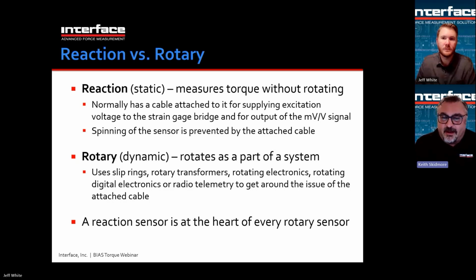A rotary sensor, on the other hand, uses some type of scheme to allow it to spin round and round without the cable becoming an issue. That could be slip rings, rotary transformers, or a rotating electronic scheme with, say, induction power transfer, which could be digital or analog. You can even use radio telemetry to broadcast the data signal across using, say, 2.4 gigahertz Wi-Fi, for example. Basically, a reaction sensor is at the heart of every rotary sensor. So you make a torque sensor, and then instead of soldering a cable to it, you add extra things to the sensor to allow it to rotate.